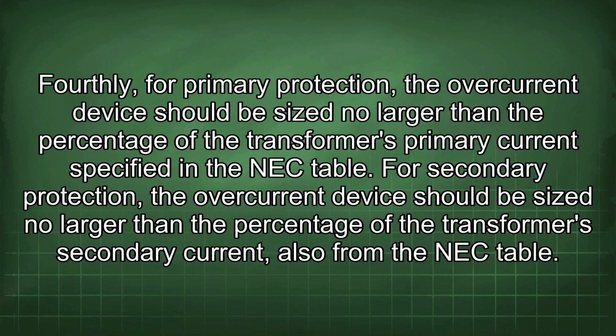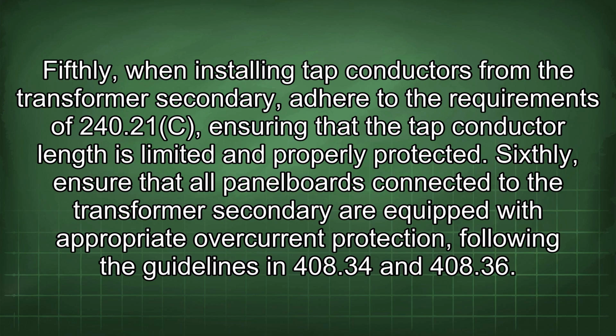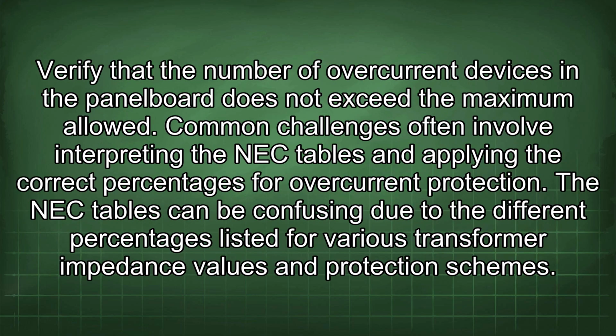Fourthly, for primary protection, the overcurrent device should be sized no larger than the percentage of the transformer's primary current specified in the NEC table. For secondary protection, the overcurrent device should be sized no larger than the percentage of the transformer's secondary current, also from the NEC table. Fifthly, when installing tap conductors from the transformer secondary, adhere to the requirements of 240.21c, ensuring that the tap conductor length is limited and properly protected. Sixthly, ensure that all panel boards connected to the transformer secondary are equipped with appropriate overcurrent protection, following the guidelines in 408.34 and 408.36. Verify that the number of overcurrent devices in the panel board does not exceed the maximum allowed.